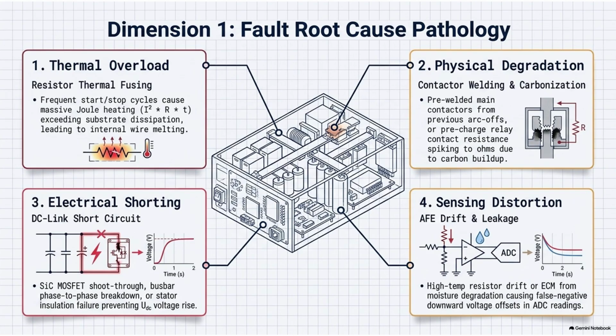It conducts massive currents where a standard wire would just melt. If the insulating tape between a positive and negative bus bar degrades, you get a hard short circuit. Same with the electric motor itself. It's full of tightly wound copper wire, the stator windings. If the thin enamel insulation on that wire flakes off from heat, bare copper touches the grounded metal casing.